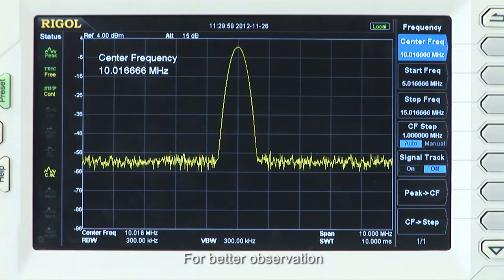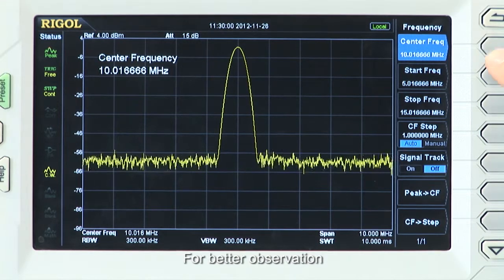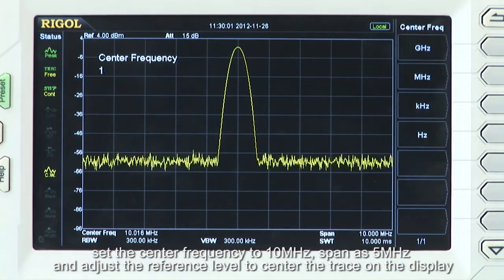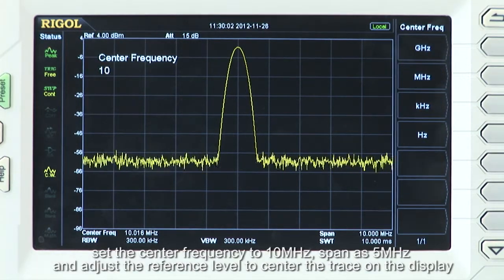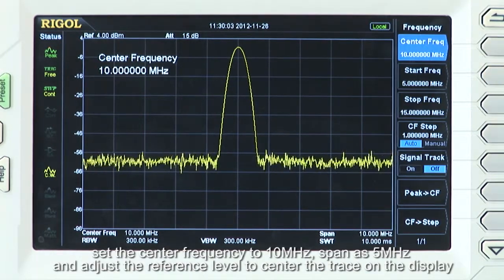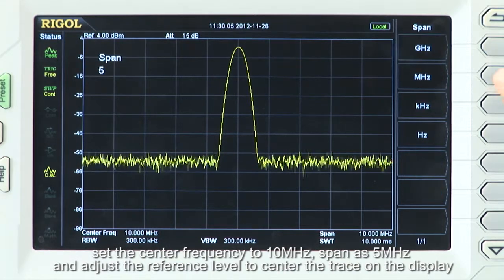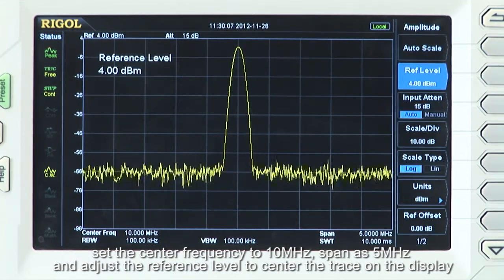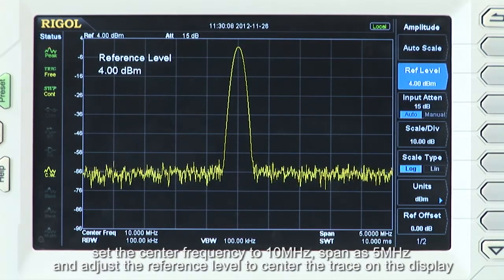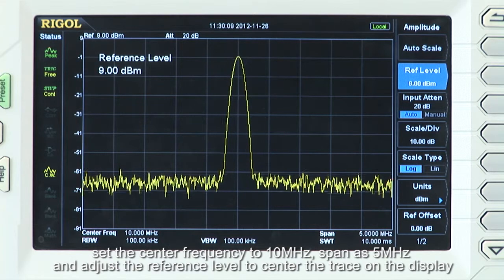For better observation, let's set the center frequency to 10 MHz, adjust the span to 5 MHz, and take a look at the reference level to center the trace on the display.